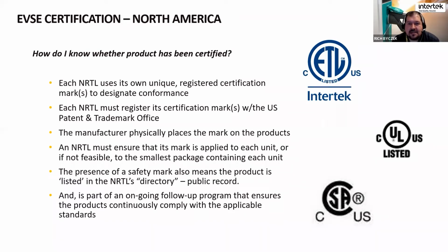In EVSE, manufacturers may adjust the look and feel of a device in ways not critical to safety, and they're free to do so. But they're not free to make changes that could affect the results of the initial evaluation or compromise the safety verified by the NRTL. That's another stand the NRTL program rests on—ongoing production must meet the same safety criteria as the initial tested samples.